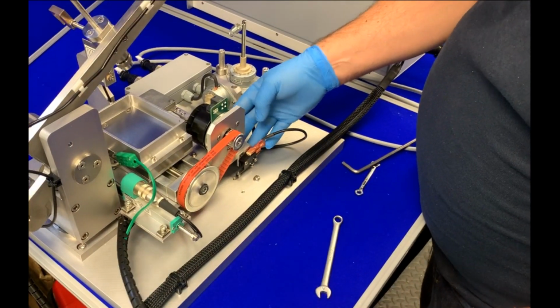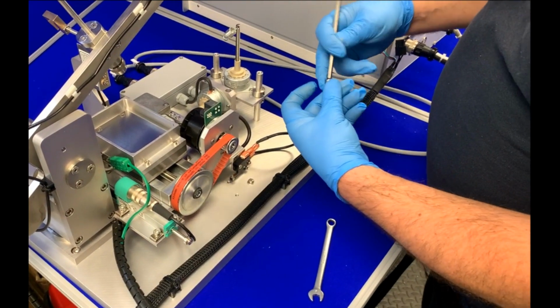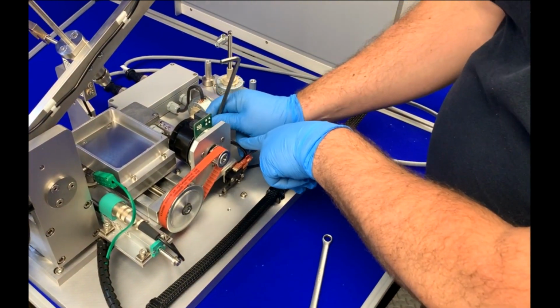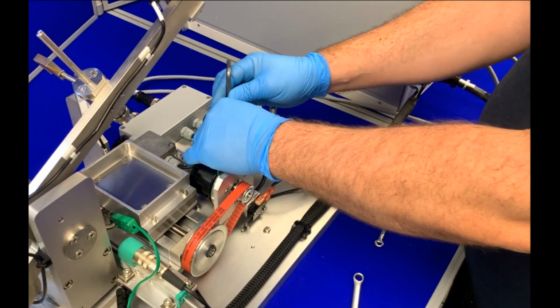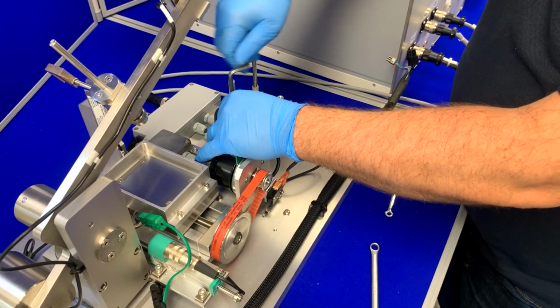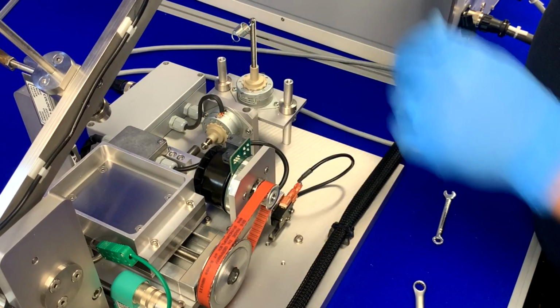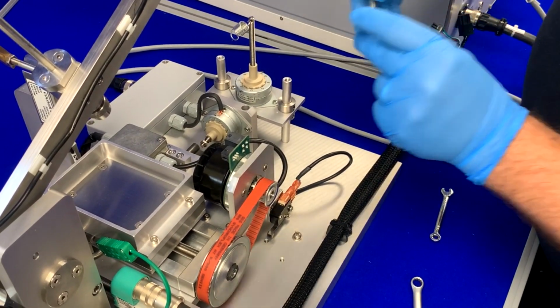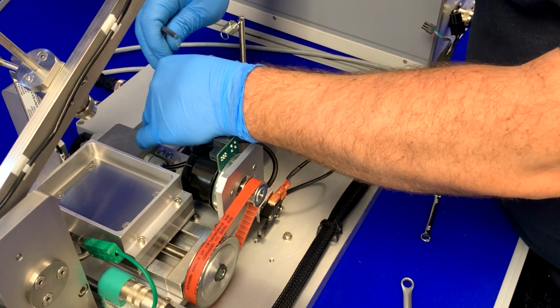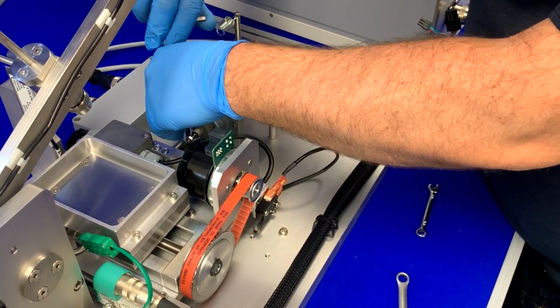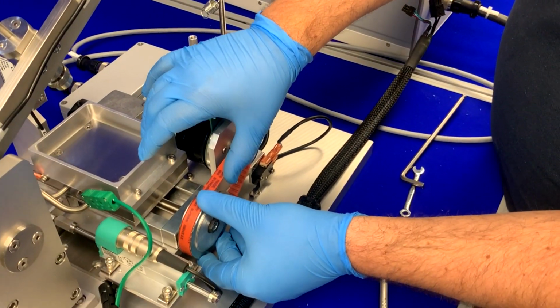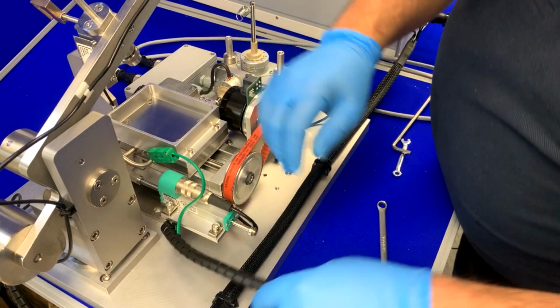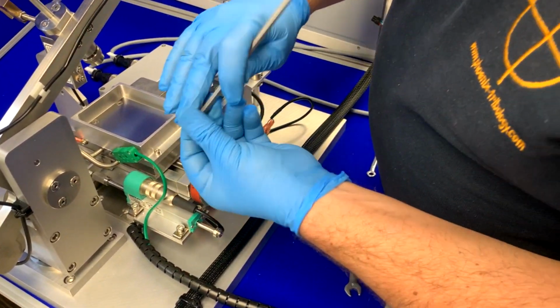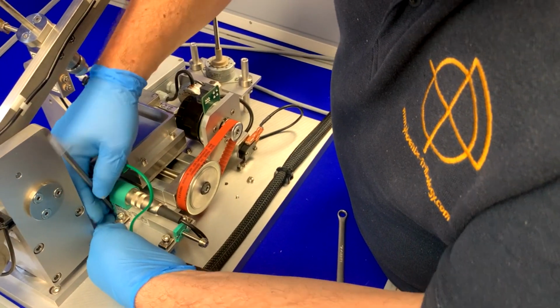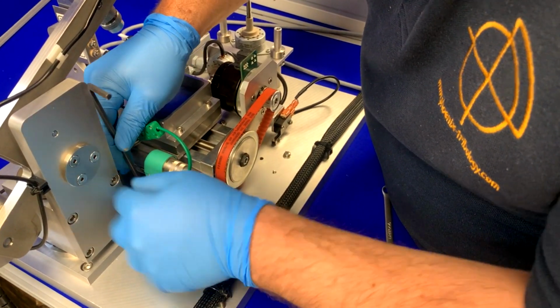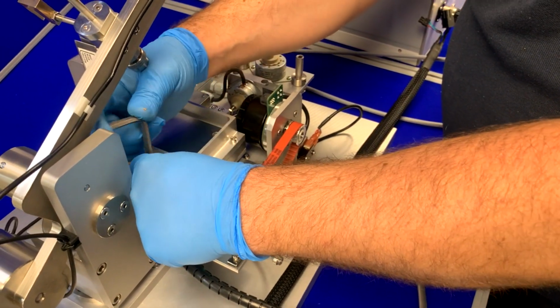Secure the slide with the 4 cap head screws provided, and remember that when sliding the carriage to expose the screw holes, lift the home switch roller lever so it doesn't get bent. Slide the carriage to the right and wind the indexing motor lead screw to engage with the tapped hole on the carriage. Secure the lead screw with the nut.